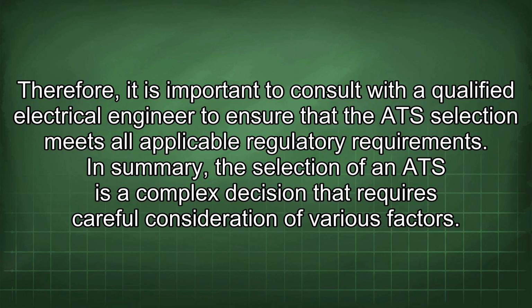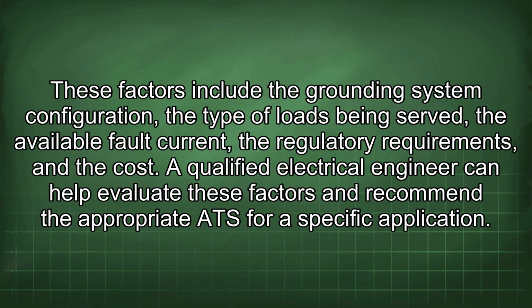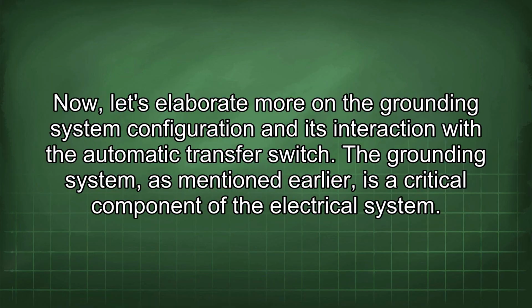regulatory requirements. In summary, the selection of an ATS is a complex decision that requires careful consideration of various factors. These factors include the grounding system configuration, the type of loads being served, the available fault current, the regulatory requirements, and the cost. A qualified electrical engineer can help evaluate these factors and recommend the appropriate ATS for a specific application. Now, let's elaborate more on the grounding system configuration and its interaction with the automatic transfer switch.